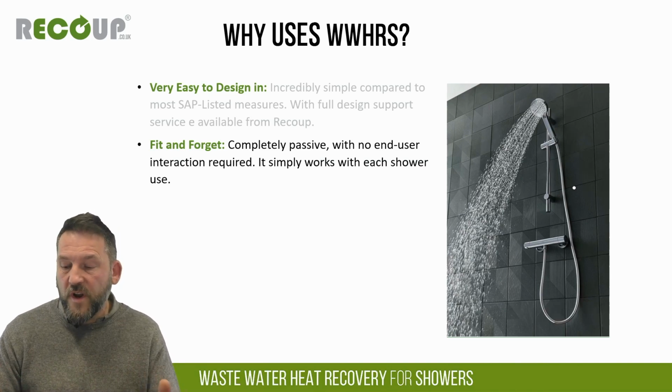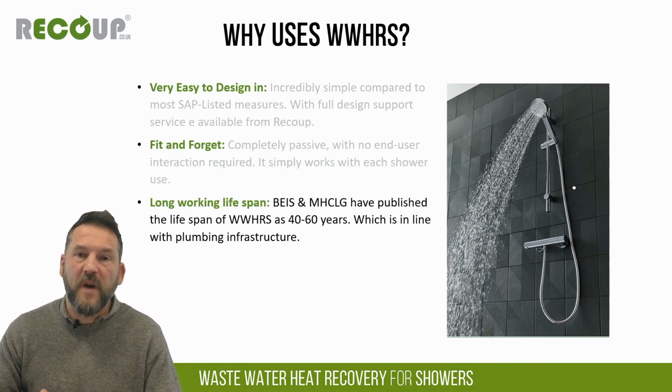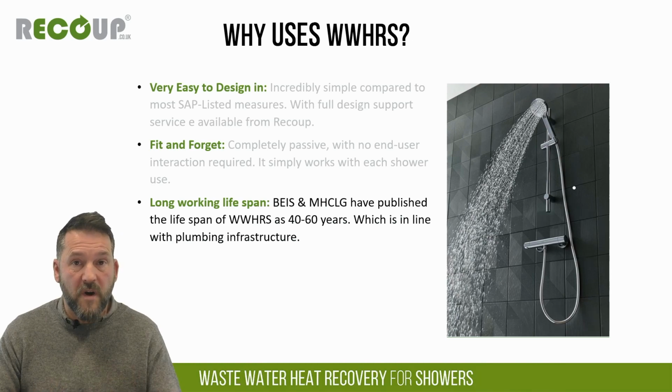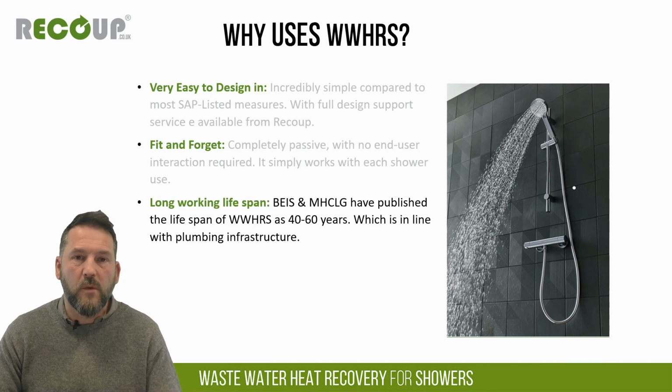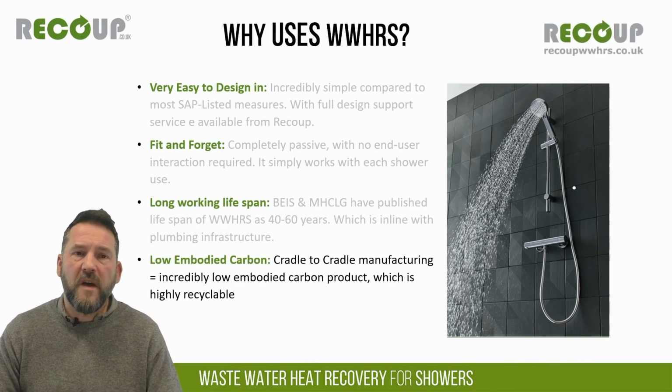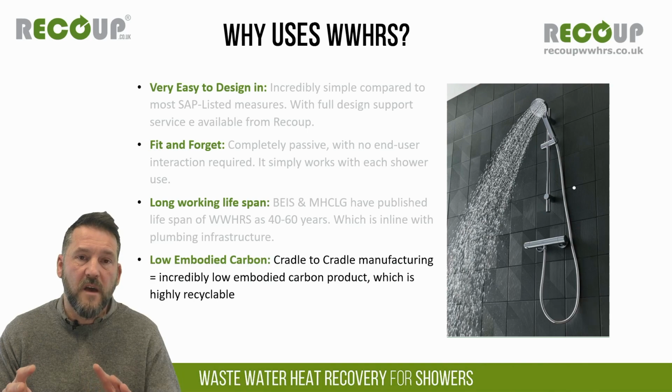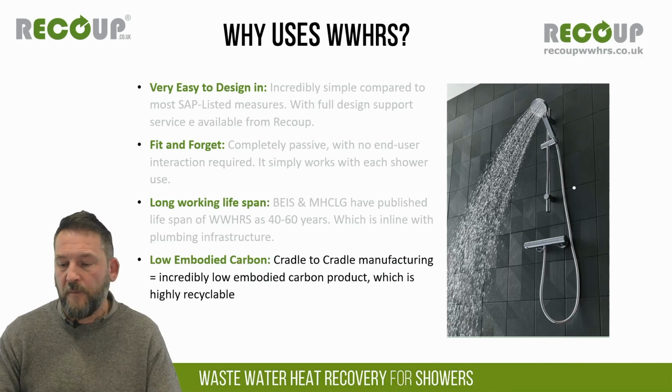Essentially a fit and forget product, and it has a very long working lifespan. So BEIS attribute around 40 to 60 years working lifespan for the vertical pipe systems, and around 25 years for the horizontal systems, as they haven't been in the market as long. But if you compare that to the expected working lifespan of a boiler or an air source heat pump, for example, it really is significantly longer. And then finally, for those who are working more progressively, we have a very low embodied carbon with our product. I'll go into it with a couple of slides towards the end, but it's very low embodied carbon because it's highly recycled and highly recyclable materials used.